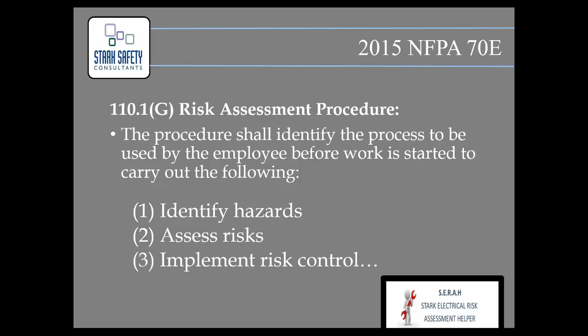Bottom line, it needs to be done. Looking at the warning label, we only see hazard information. If this is an existing label, your RFP needs to spell out whether you're requiring the provider to do the risk component or just the hazard component—it could be you're only asking for the arc flash piece. Be careful there's no language also requiring the risk assessment component unless you intend that, and if you do, detail how that process will be carried out.